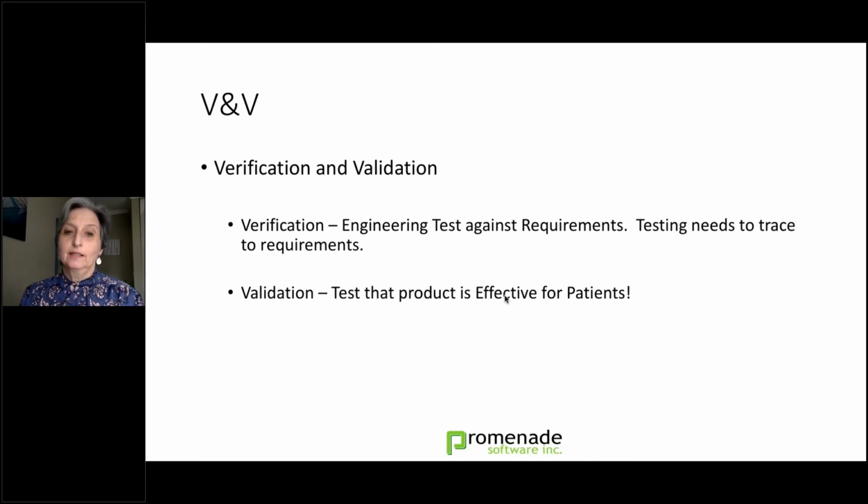Validation, that's the test that proves this is effective for patients. We've had clients, again, when they're coming in a little bit less experienced, sort of forget that indeed you need to fully validate that this works and provide evidence to the FDA that indeed the product is effective for patients. So for instance, if you're doing a COVID-19 test, you have to have some clinical evidence that it is effective and it works.